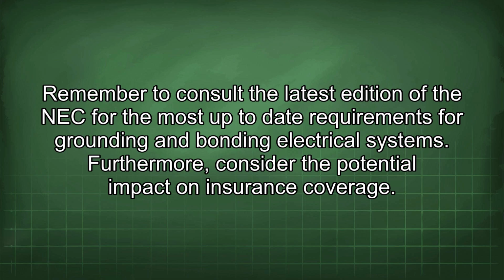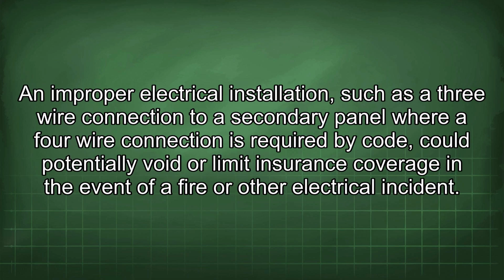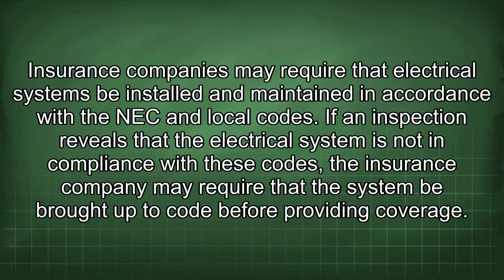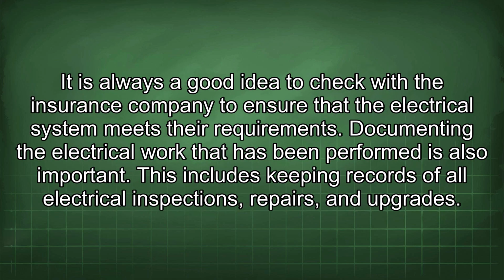Furthermore, consider the potential impact on insurance coverage. An improper electrical installation, such as a 3-wire connection to a secondary panel where a 4-wire connection is required by code, could potentially void or limit insurance coverage in the event of fire or other electrical incident. Insurance companies may require that electrical systems be installed and maintained in accordance with the NEC and local codes. If an inspection reveals that the electrical system is not in compliance with these codes, the insurance company may require that the system be brought up to code before providing coverage. It is always a good idea to check with the insurance company to ensure that the electrical system meets their requirements.